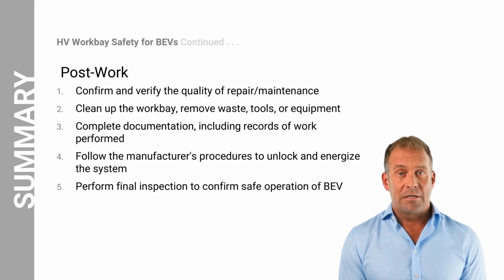In the post-work section, Step 1 is to double-check and verify the repair, service, or maintenance quality after the main work is completed. Perform functional tests to ensure the high-voltage system operates correctly. Step 2. Clean the work area, removing waste, tools, or equipment. Step 3. Complete all necessary documentation, including records of the work performed, any voltage measurements, and the completion date.